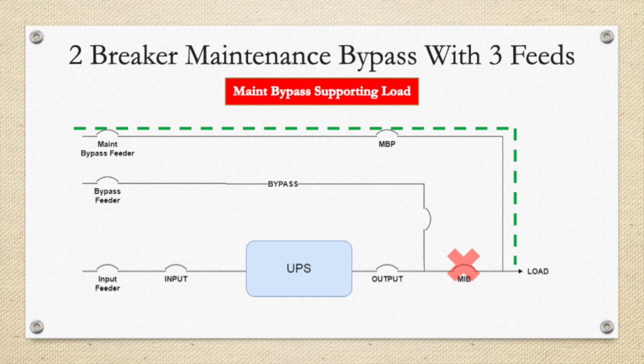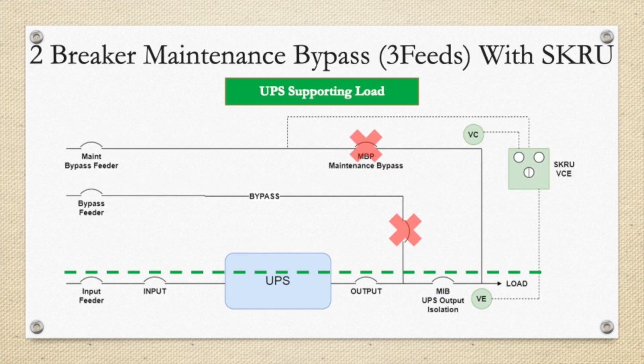This next drawing, we're going 1 step further, and this is the best. 2-breaker maintenance bypass, 3 feeds, and we have the SKRU interlock. This benefit is going to provide us elimination of operator error. We won't be able to go to maintenance bypass until the UPS gives a signal to the SKRU unit that we are in internal bypass. So we bypass the UPS, it allows us to unlock the Kirk key on the maintenance bypass, close it, unlock the MIB, open it. So first drawing again is showing us online.